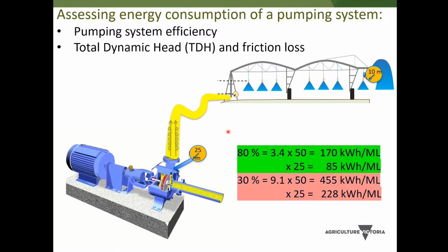So you can see both that pressure, the total dynamic head or the total pressure required of the irrigation system, and the efficiency of the pumping system are both really important in minimising energy costs. You can have a highly efficient pumping system, but if it's pushing against a poorly designed irrigation system, then your pumping costs are still going to be high. And we actually find a lot of the improvements are in the irrigation system.